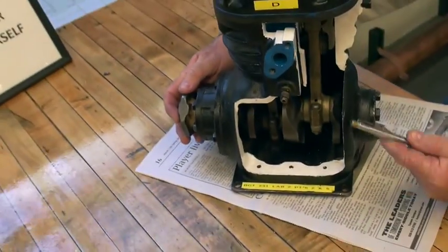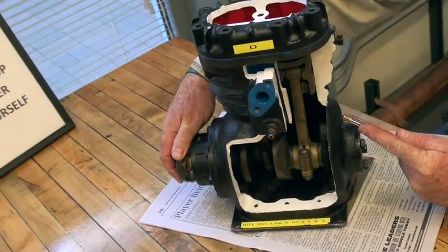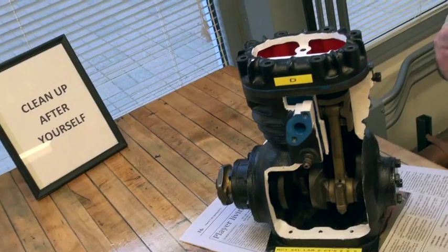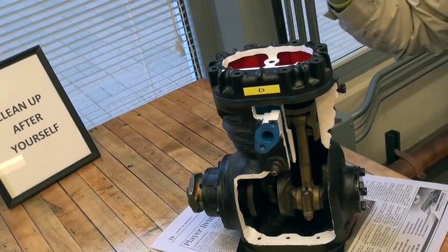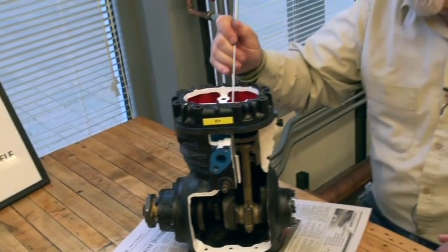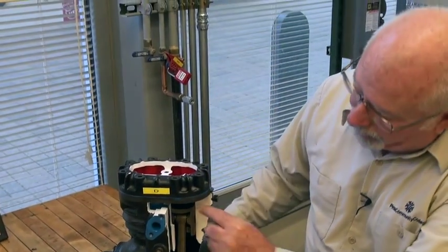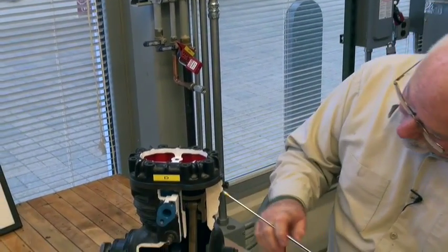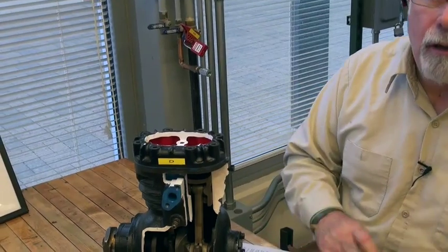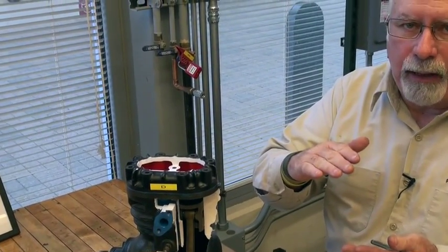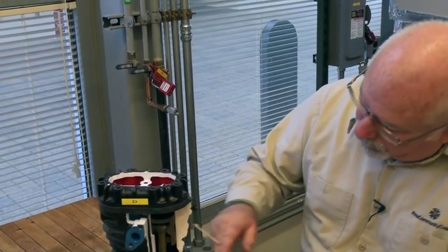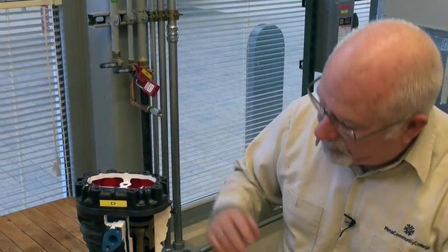As that compressor draws down, at some point the pressure on top inside this channel and the pressure inside the cylinder are going to equal, and then the pressure is going to drop into a negative pressure somewhere as this compressor valve drops.